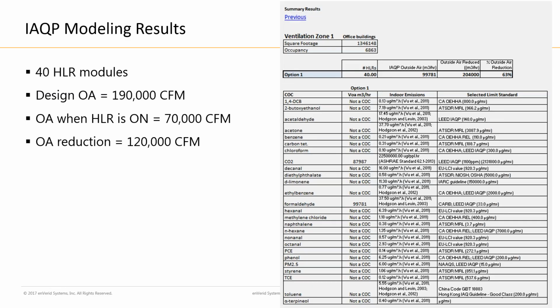The net result there was fantastic indoor air quality within the space, meeting several LEED requirements as well, and those LEED limit standards. We reduced outside air 63%, which on this 1.3 million square foot facility meant that we reduced outside air 120,000 CFM. This was a retrofit application that actually paid for itself in less than a year, thanks also in due part to the utility rebates and measurement and verification that was done.